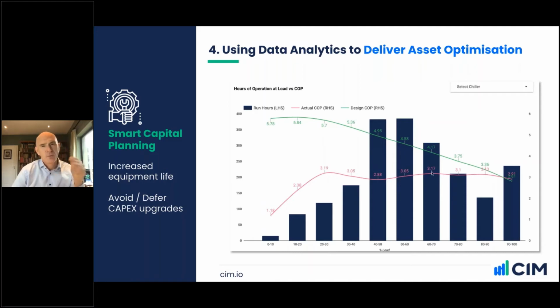So what this allows us to do is get that data set and plug it into the models for new chiller purchases, and we can use actual data instead of cut sheet data to say this is how it should operate. We can use the data set from the site, typically a couple of years of historical data, to say this is how it will actually operate. And this allows the clients to do that kind of detailed assessment before they have to spend any money on capital equipment. And that's smart capital planning.